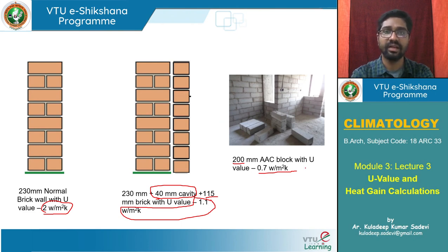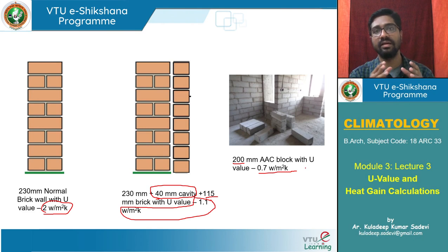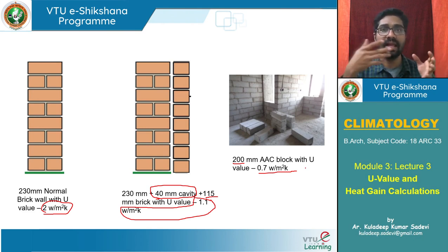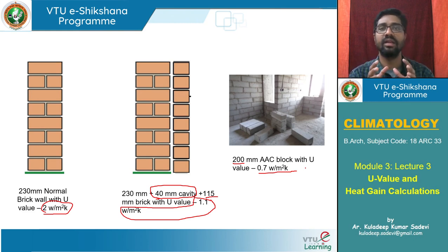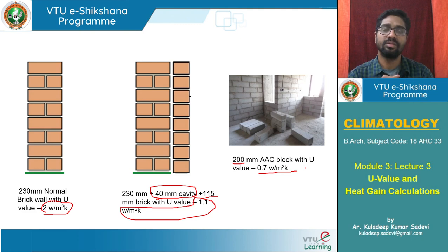We can change the material and thickness to change the overall U-value. By adding 230 mm brick with an air cavity plus another 115 mm layer, we reduce the U-value to 1.1 W/m²·K. Instead, using 200 mm AAC blocks can reduce it to 0.7 W/m²·K directly. The material choice should be based on outdoor temperature variations, time lag needed, and thermal mass desired.